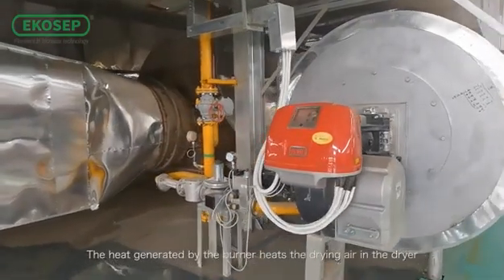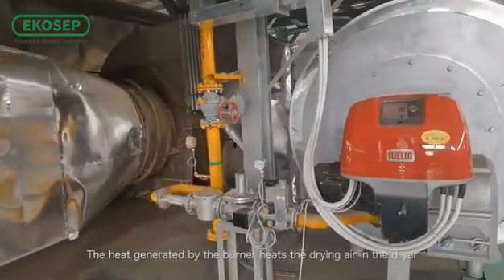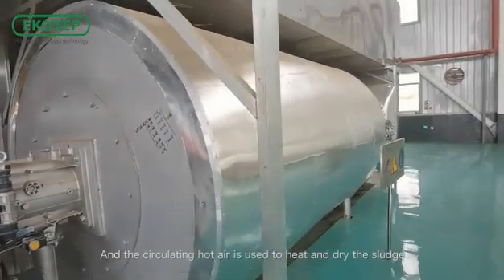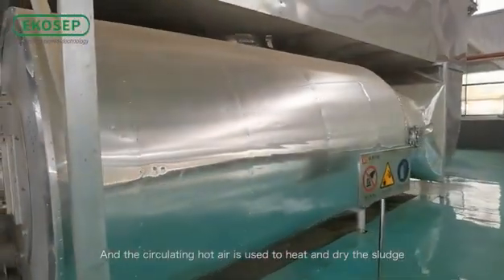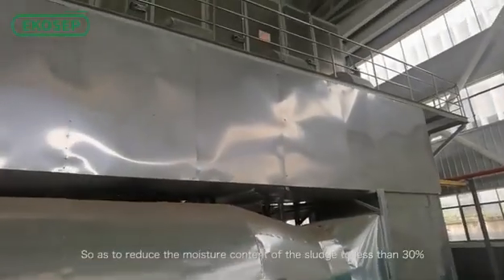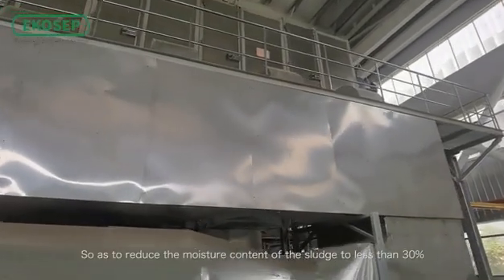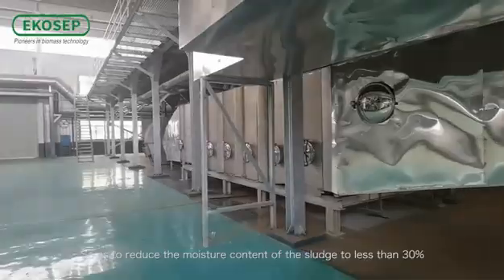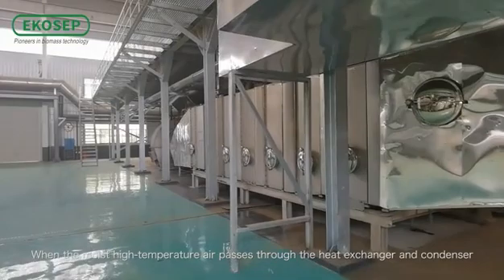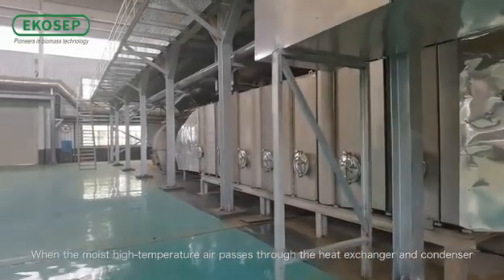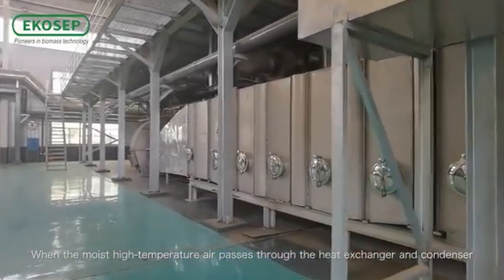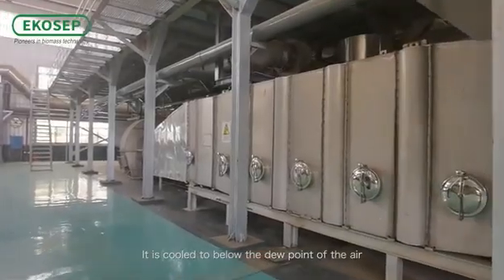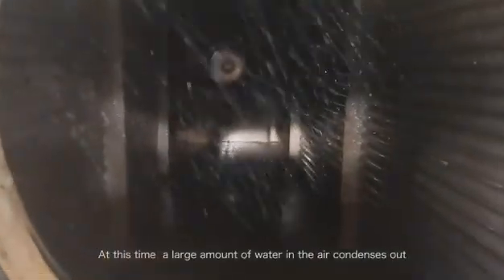The heat generated by the burner heats the drying air in the dryer, and the circulating hot air is used to heat and dry the sludge, so as to reduce the moisture content of the sludge to less than 30%. Then the moist high-temperature air passes through the heat exchanger and condenser. It is cooled to below the dew point of the air. At this time, a large amount of water in the air condenses out.